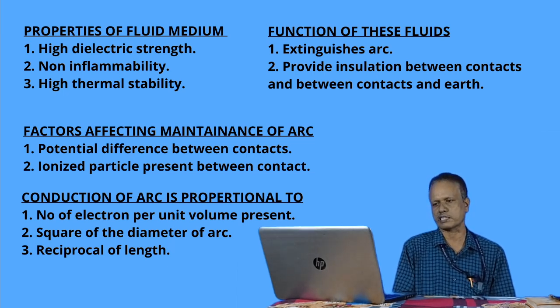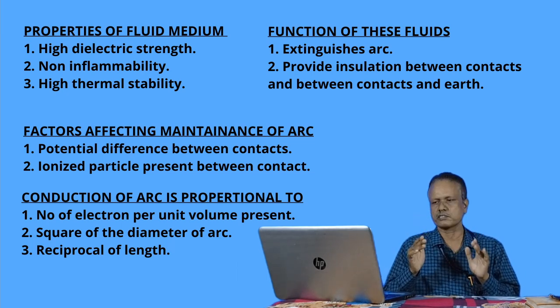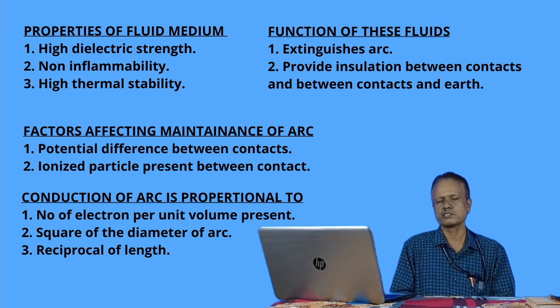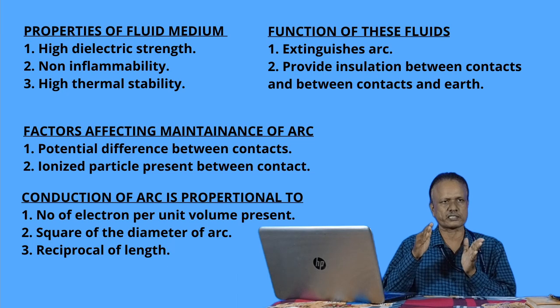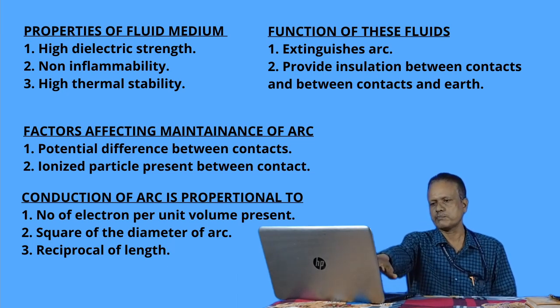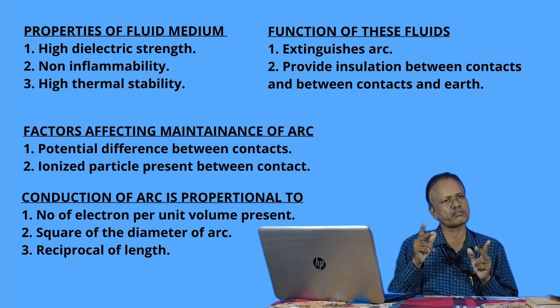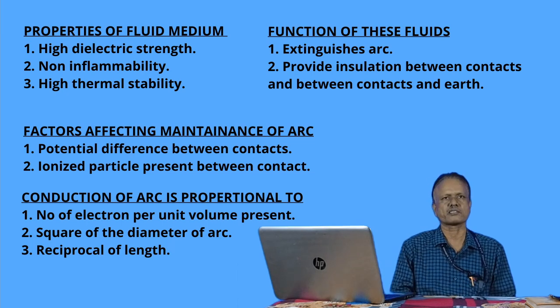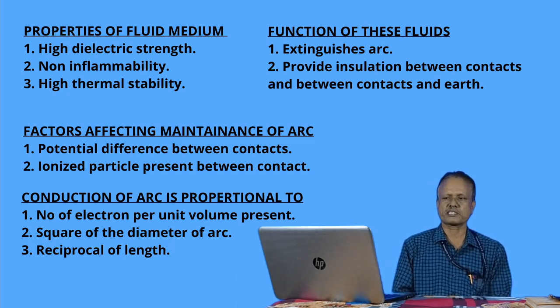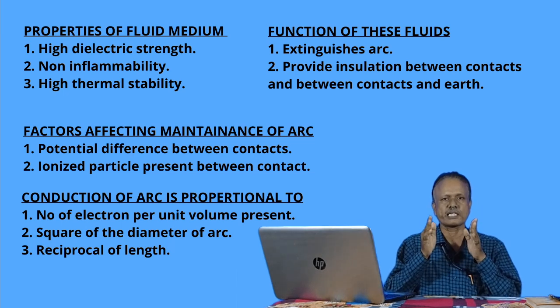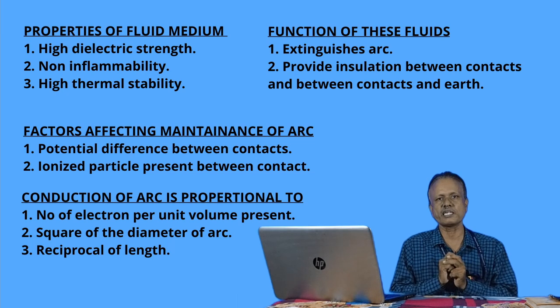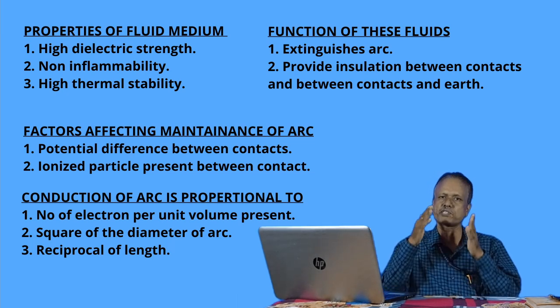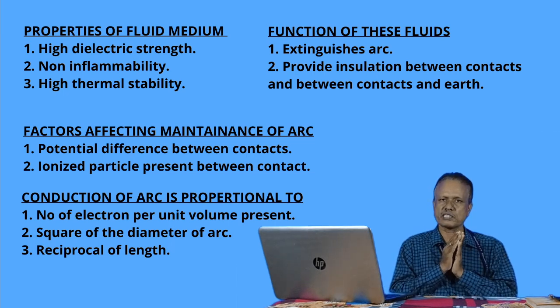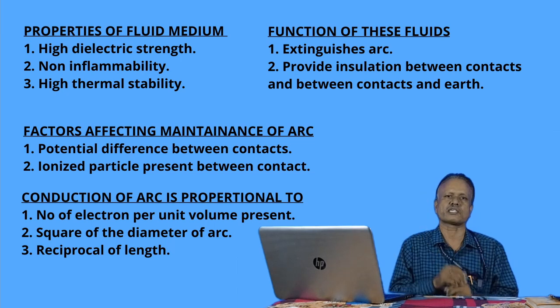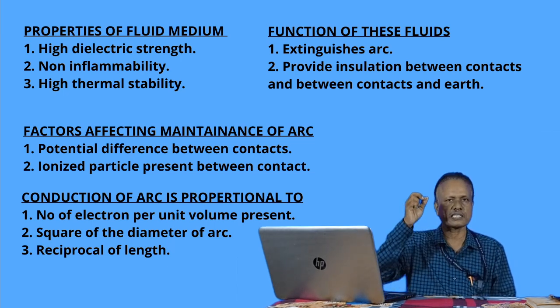If we go to the maintenance of the arc, how the arc is maintained between these 2 contacts, we will observe the following 2 things. If a potential difference is there between these 2 contacts, then the arc will persist. Similarly, if ionized particles are present between these 2 contacts, then also the arc is maintained. So these 2 factors are responsible for maintaining the arc. But our requirement is what? We want to extinguish the arc. That is why we can either decrease the potential difference between these 2 contacts, or sweep away the ionized particles between these 2 contacts. So these are the 2 things on which the maintenance of the arc depends.